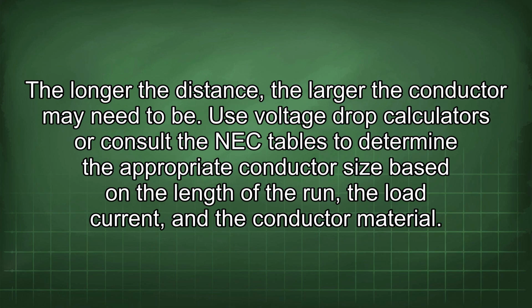The longer the distance, the larger the conductor may need to be. Use voltage drop calculators or consult the NEC tables to determine the appropriate conductor size based on the length of the run, the load current, and the conductor material.